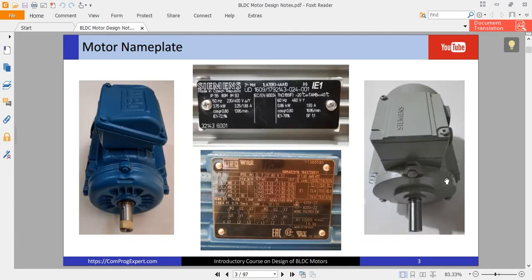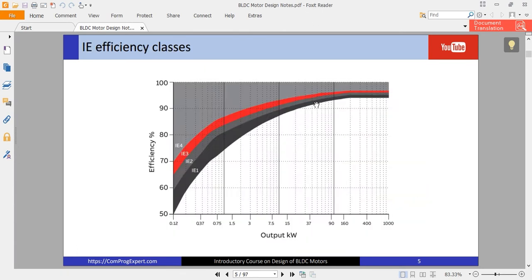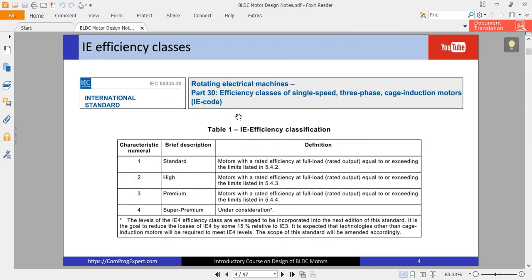The two motors considered here are IE1 efficiency, as you can see on the name plate — IE1. In this standard, we have equations and procedures to calculate the efficiency of every class versus its rating and its frequency. This standard is for single-speed, three-phase cage induction motors.